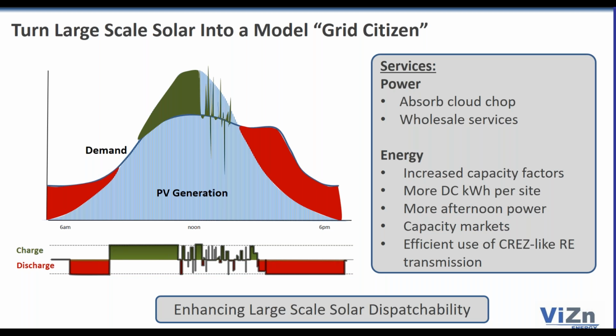But the batteries can also increase capacity factors. You'd typically put 110 to 120 megawatts of DC solar on a 100 megawatt AC interconnect, with 100 megawatt transformers and substation. With energy storage, you can drive that to 140 to 150 megawatts of DC solar, with 20 to 30 megawatts of batteries to drive more afternoon power. Just saw yesterday that Hawaii is going to come out with 2 different tariffs, one set for solar delivered between 5 and 10 p.m.—a time of use energy application combined with the power requirements we've illustrated here.